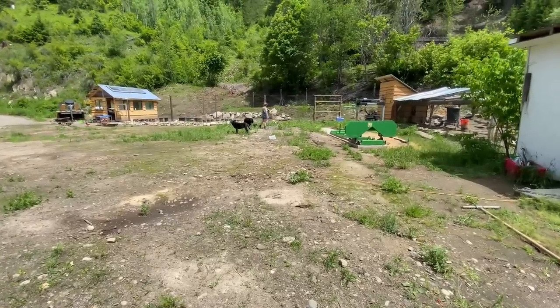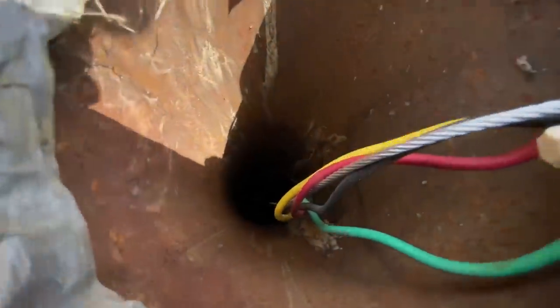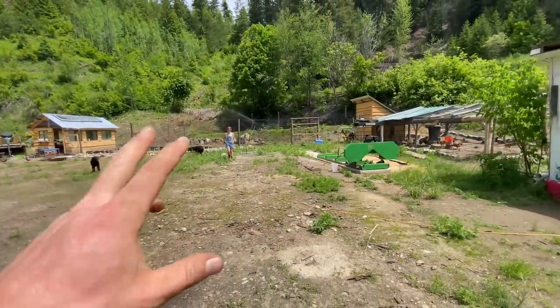We're gonna make sure the pump cycles and everything works. So once that runs itself to a low enough pressure, about 40 PSI, we should see this pump kick on. Probably we'll be able to hear it. See what happens. Can kind of see the water level on the side there. Once that pump kicks on, that should drop. There it goes. All right, everything seems to be going just fine.